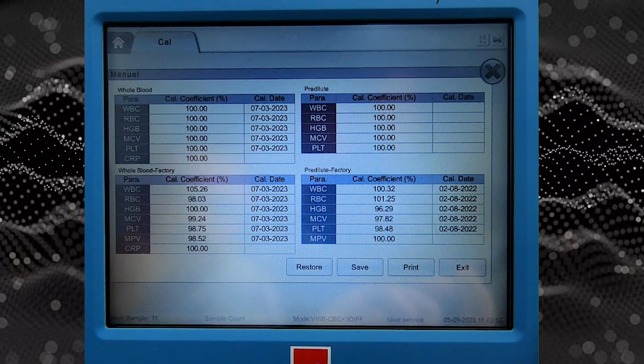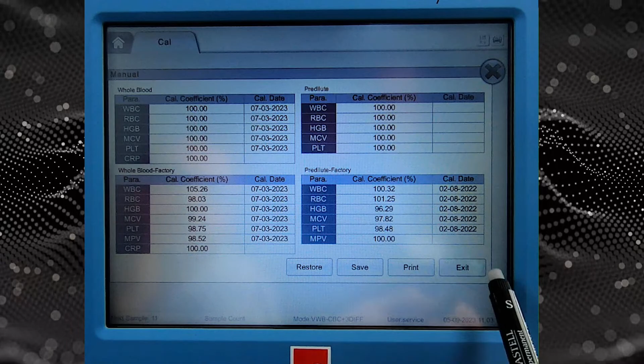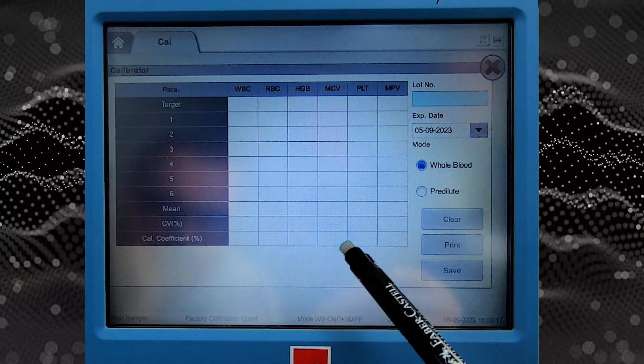So this is calibration. The manual actually allows you to change the calibration coefficient manually. Since we are logging in as a service, we have an additional set of calibration factors, and those which are here are the factory set calibration, right? And this is the user available calibration. When we are logging in as a service, we are changing the factory calibration. If we go to manual, we will not change anything here, but those values will change. But if we are logging in as an administrator, those things will be modified, because this is not visible for the administrator.